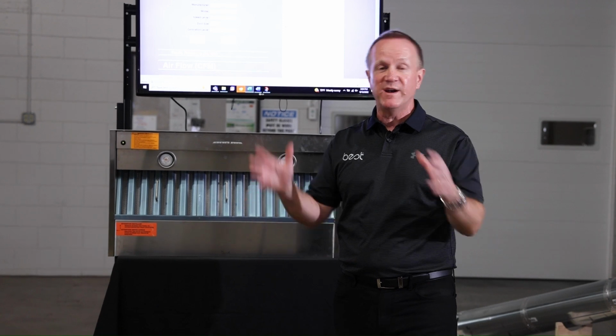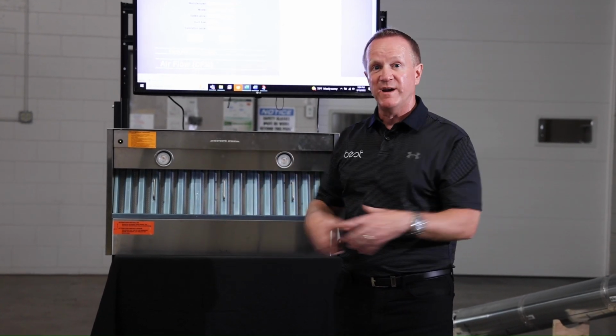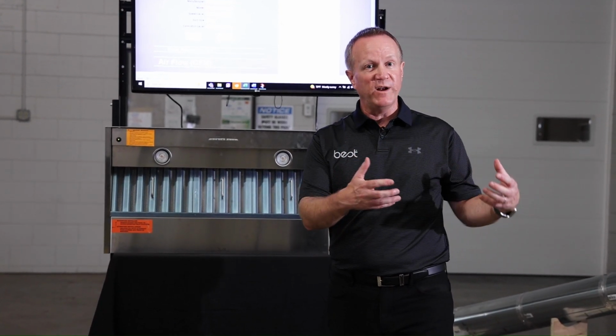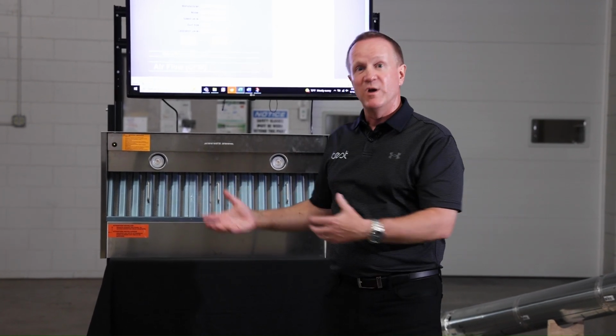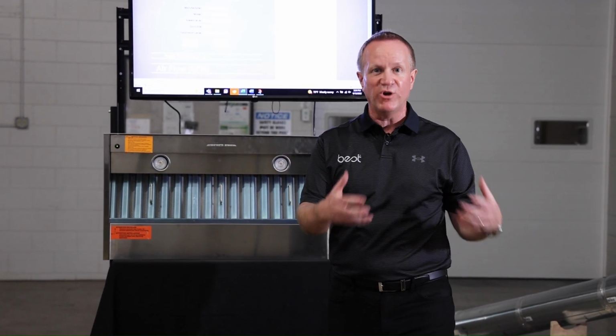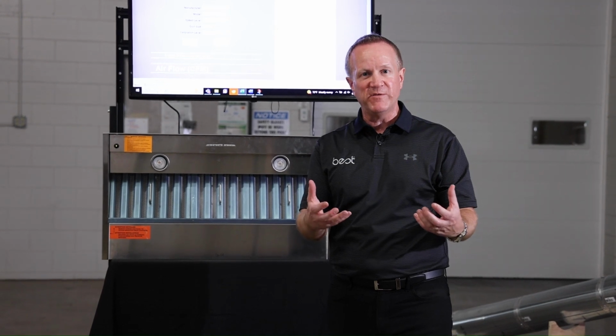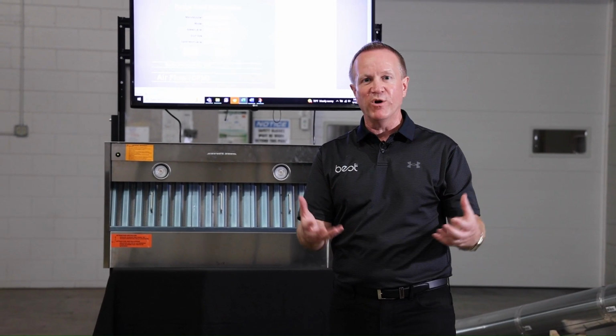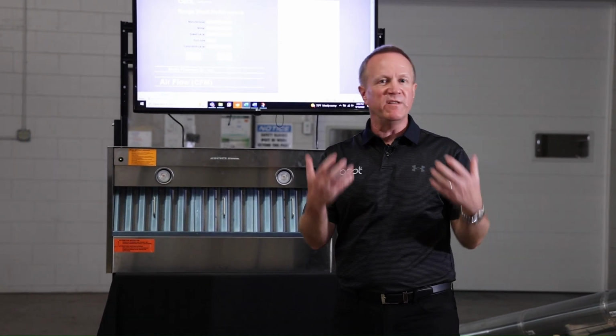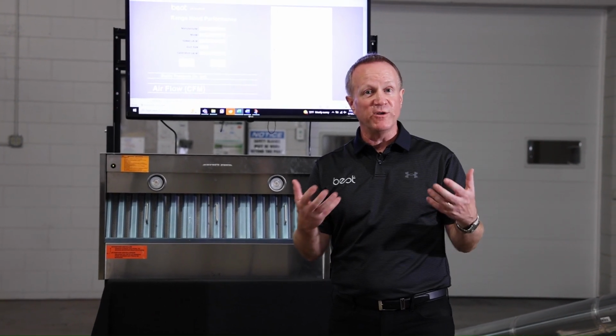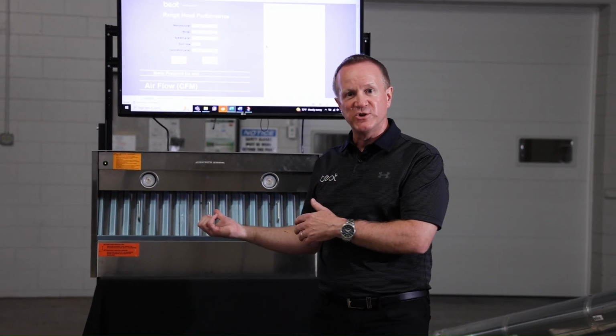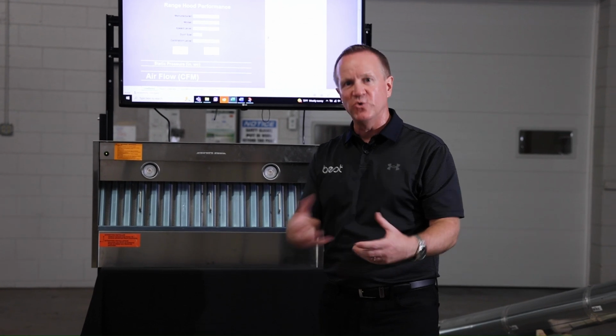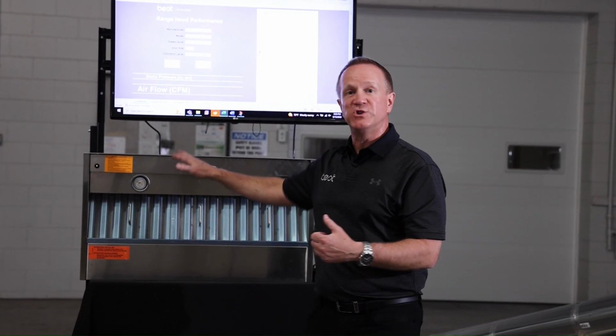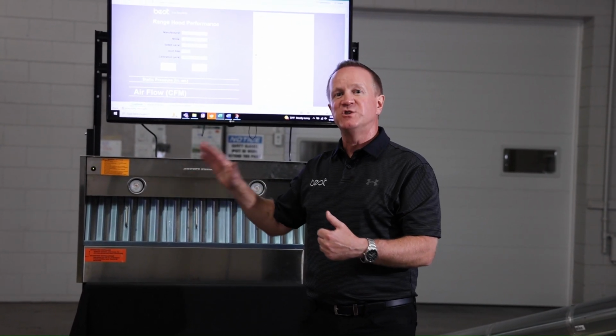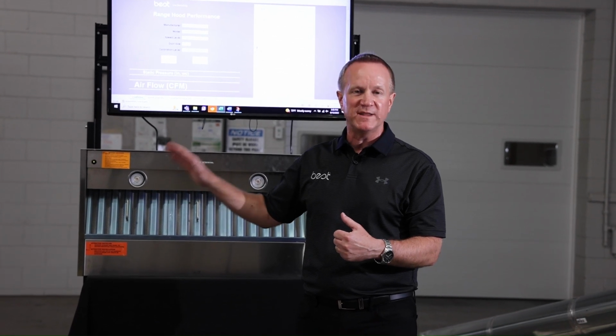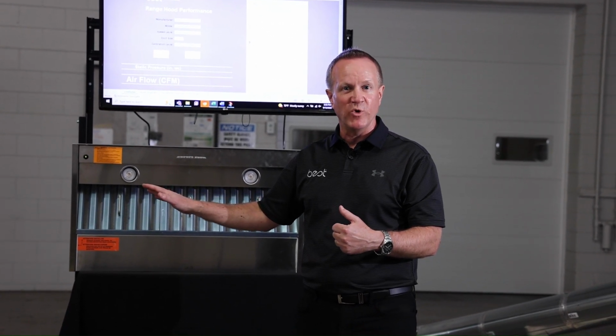So we could calibrate it at 4 feet, we could calibrate it at 30 feet, we could calibrate it with the roof cap on. Here, we're going to calibrate it as installed in a home, with that 30 feet of ducting, with the roof cap already installed. This would be the last thing that an installer should be doing once they install the hood. As they're gathering their tools, as they're picking up, they should do the calibration to ensure that the client is going to get that 600 CFM performance.